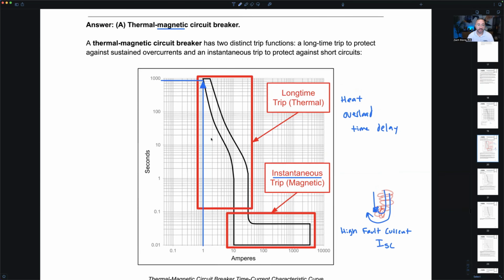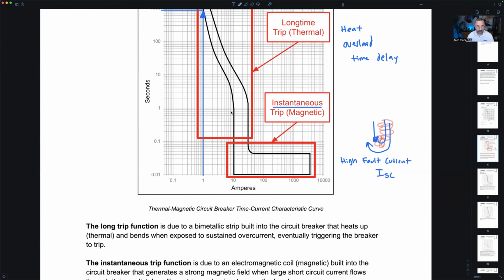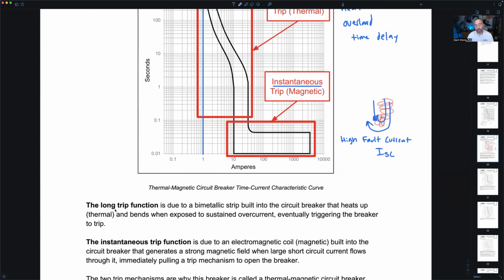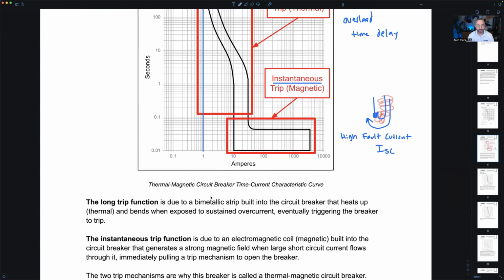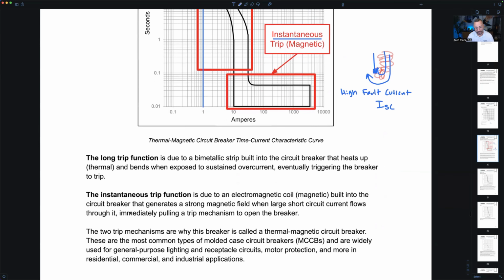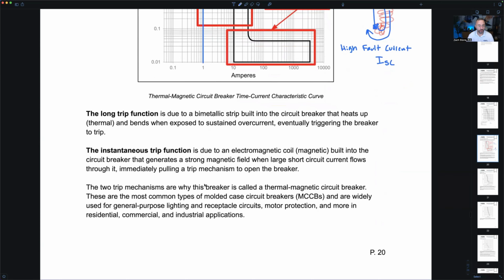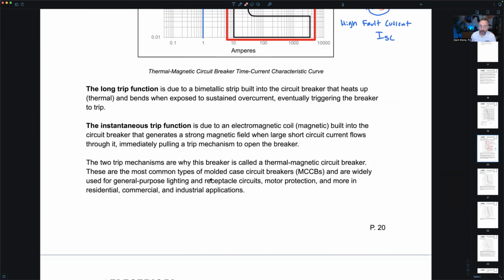So this was the TCC curve in the problem, and it's for a thermal mag breaker. We talked about the long trip or the thermal trip or the overload region, right? We talked about the instantaneous trip function. Good point to point out is this is the most common. Anyone here know what's a molded case circuit breaker, MCCB? What does molded case mean? That's when you have a breaker made out of plastic, molded plastic. The case of the breaker is molded in plastic.